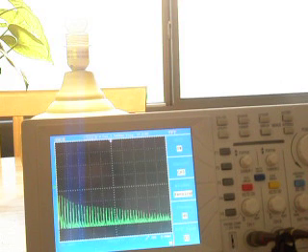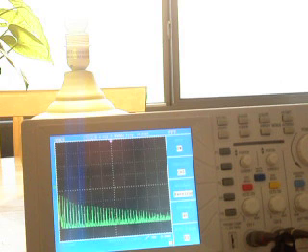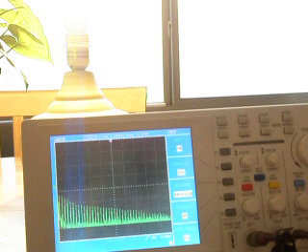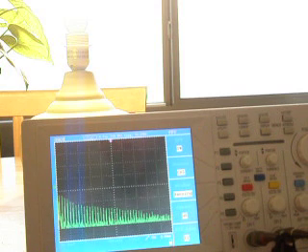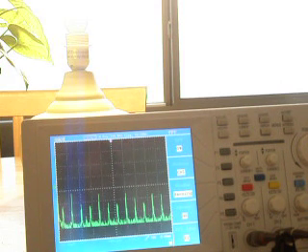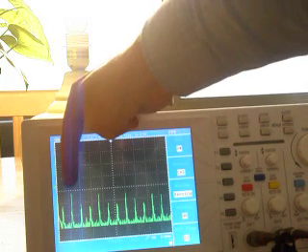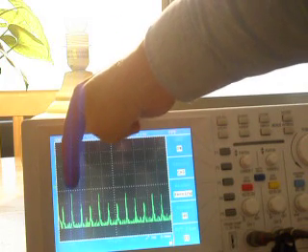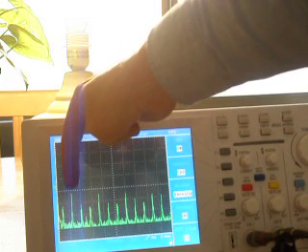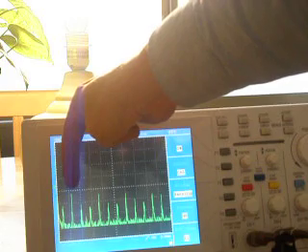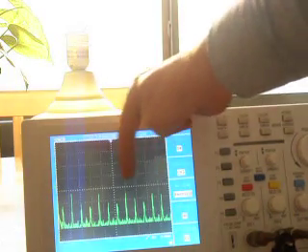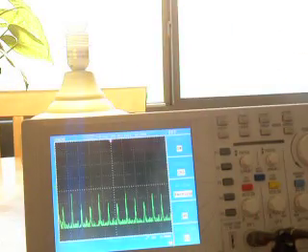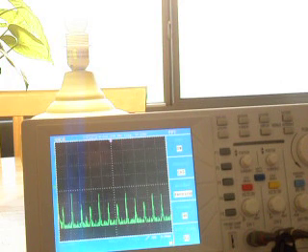We see many frequencies, and each spike is a frequency. And we're currently set on 500 hertz per division. So let's go down to 50 hertz per division and see what we get. So that's 50 hertz per division. Now right here, this is typical of the utility system. This is the frequency that the utility system runs at. But you can see we have all these other frequencies. And all these other frequencies are coming from the electronics on that light bulb.